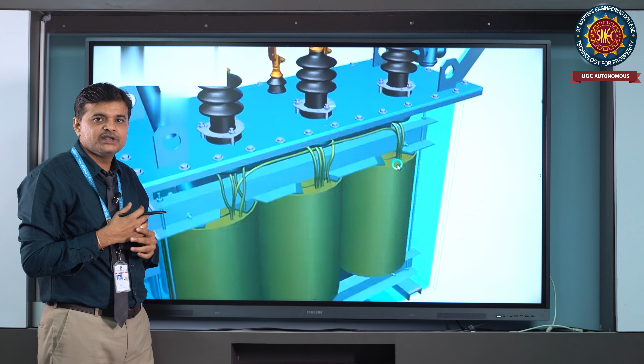Because of the tappings, the tappings will be provided on the HV side. Why do we need tappings? What is the use of tappings? Suppose the household voltage is around 420 to 430 volts, and the voltage becomes less or more. By using on-load tap changers, we can adjust the voltages. That is the reason the HV winding is provided outside and the LV winding is provided near the core. We can reduce the insulation of the core.